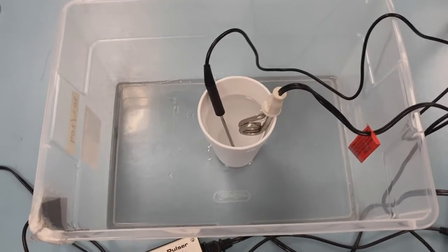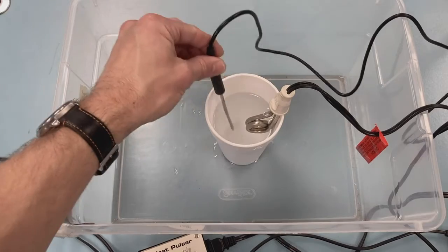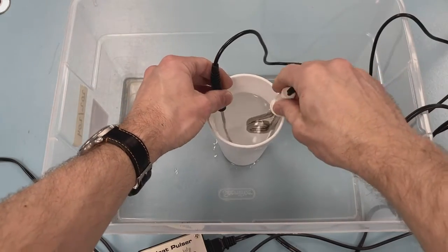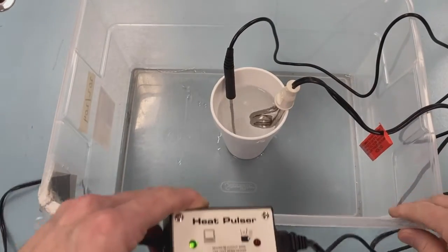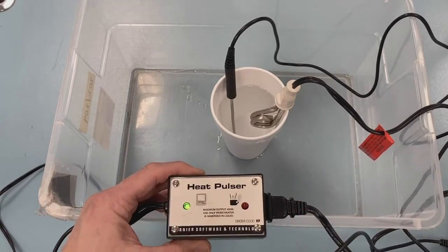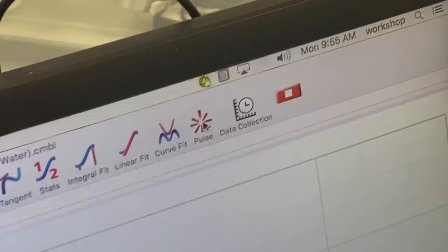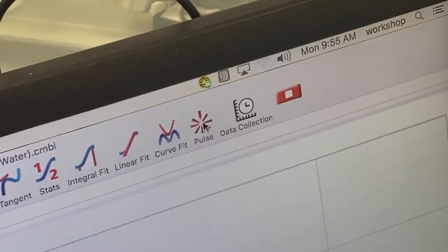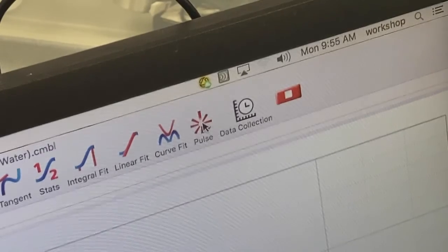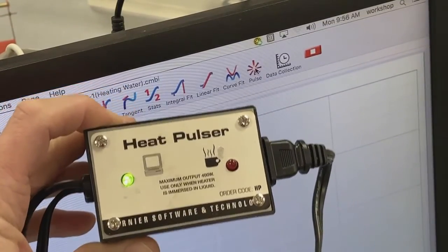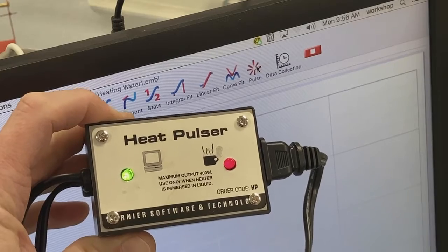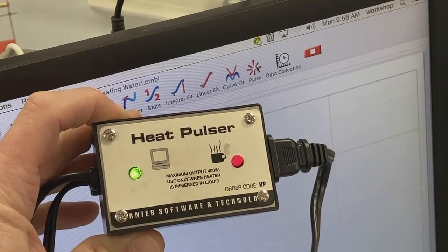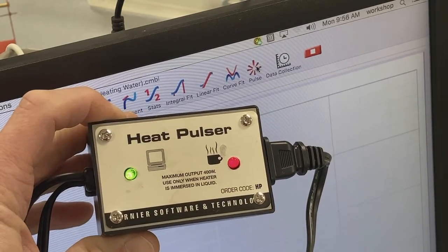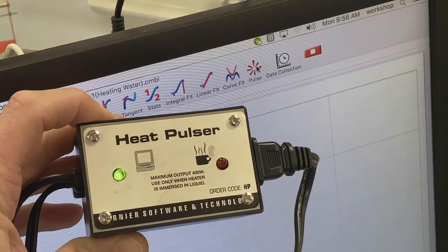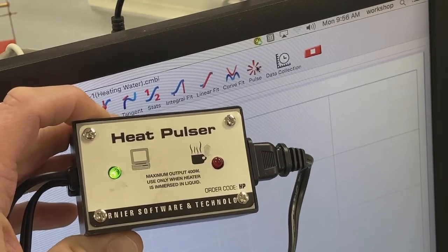With this setup, I'll have a temperature probe in the immersion heater, and the immersion heater is connected to the Heat Pulser. You'll notice there's a pulse button now up on the top panel. If we look at the Heat Pulser at the same time, when I click pulse, it turns on for a few seconds. Should be exactly 5 seconds. You might want to count the first time just to make sure it's configured correctly.